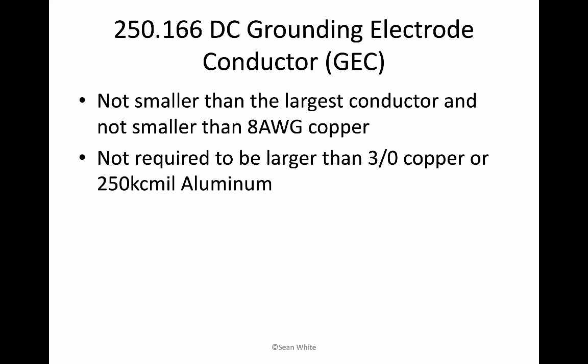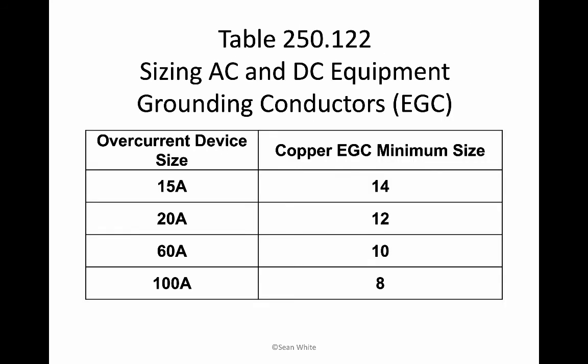And if you don't even remember what they are, if there are only 3 of them, you could go to all 3 of them. And here it is, Table 250.122. This is how to size our AC and our DC equipment grounding conductors. So if your overcurrent protection device is 15 amps or less, then you're required to use at least a 14 gauge wire. You will see that many people use a 10 gauge wire when they're using a 15 amp overcurrent protection device, because the AHJ doesn't always understand the NEC perfectly, and they might just want to see a 10 gauge wire for an equipment grounding conductor when all your other conductors are 10 gauge wire, and they're just really used to that. But it would work.